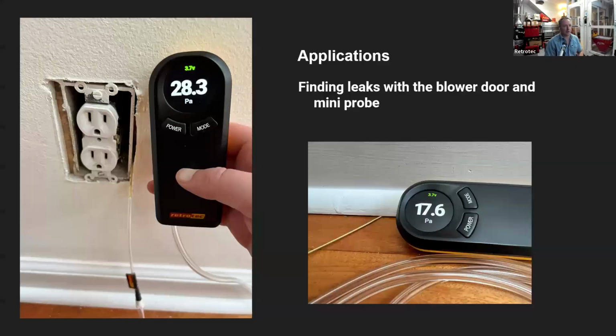The mini probe is a great counterpart for this gauge. Again, when you're using it with a blower door, if you're trying to find leaks in assemblies, that mini probe, the end of that tube is 1/16 of an inch. So you can really get into some tight nooks and crannies with it and see what those pressure differentials are. If you have a leaky wall assembly or floor, crawl space, attic, to see what that leakage profile looks like for that assembly that you're testing.